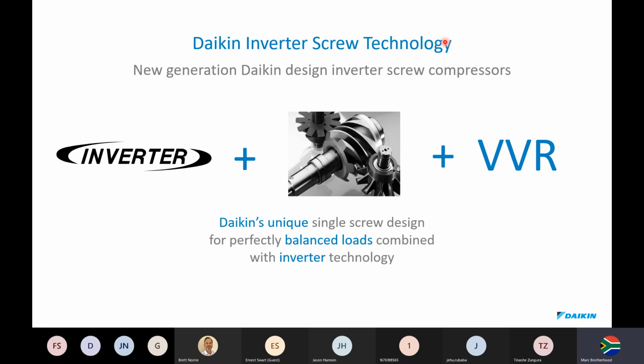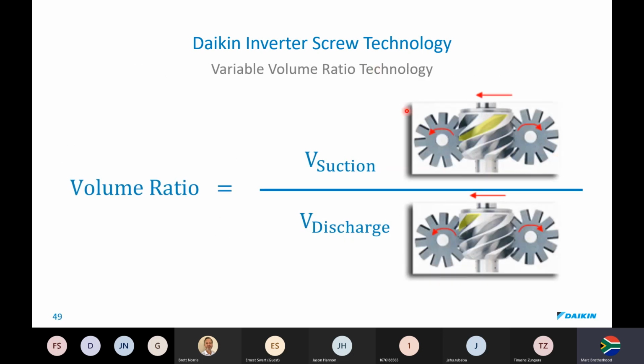Further to that, Daikin has also introduced what we call variable volume ratio to improve on our energy efficiency. So this is a bit of a complicated design, but it works on a volume ratio. It works on volume, and a ratio is a difference between two things, like 5 tablespoons of sugar and 2 tablespoons of salt. That's sort of a ratio that you would put in if you wanted to, say, cook something. We work on a very similar principle where we work with volume on the suction divided by volume on the discharge.